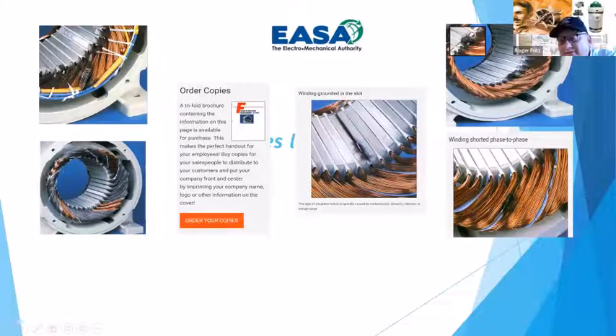And then this is showing where this blue insulation paper is. That's, again, phase to phase. So you've got 1, 2, 3 phases here. And this happened to be a 4-pole machine, you can tell, because there's 4 here. A 2-pole would only have 2 windings showing, not burnt, and then the other windings would all show burn if that was a 2-pole machine. This would be a 4-pole machine.